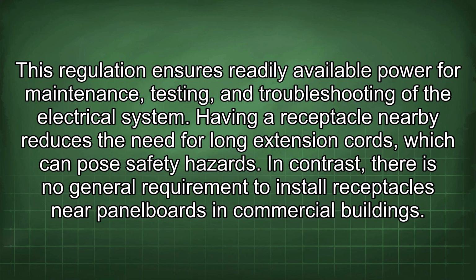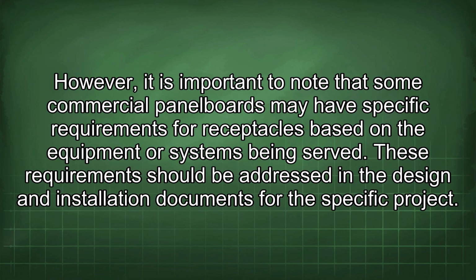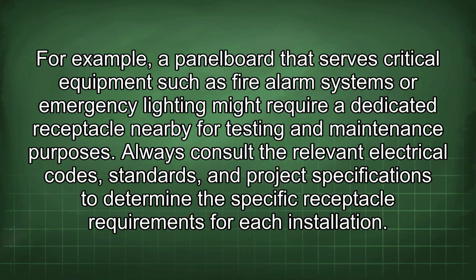In contrast, there is no general requirement to install receptacles near panel boards in commercial buildings. However, it is important to note that some commercial panel boards may have specific requirements for receptacles based on the equipment or systems being served. These requirements should be addressed in the design and installation documents for the specific project. For example, a panel board that serves critical equipment such as fire alarm systems or emergency lighting might require a dedicated receptacle nearby for testing and maintenance purposes. Always consult the relevant electrical codes, standards, and project specifications to determine the specific receptacle requirements for each installation.